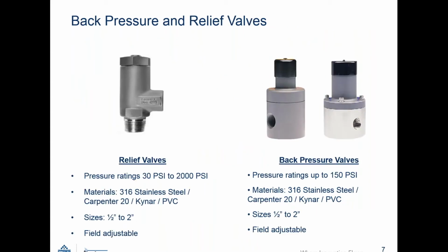Back pressure relief valves. Relief valves are a requirement for most applications. They are a safety device for the piping that's in the system. These are used when systems need to protect either the piping or the pump. Generally, some pumps have what they call internal relief valves to protect the pump.